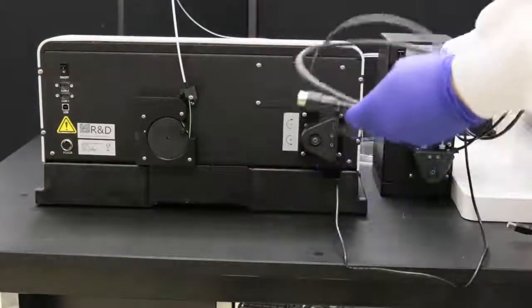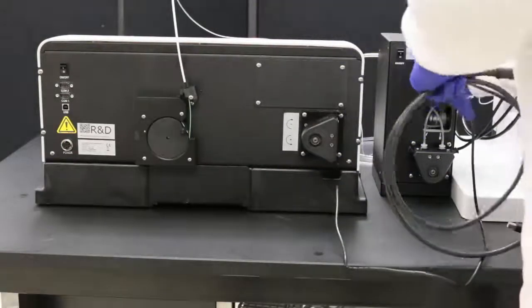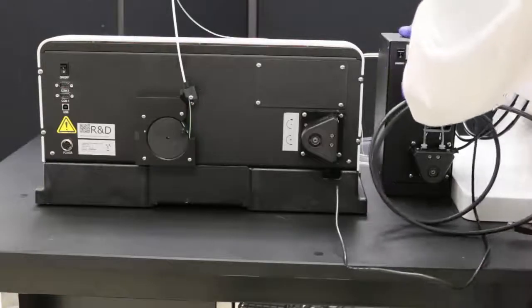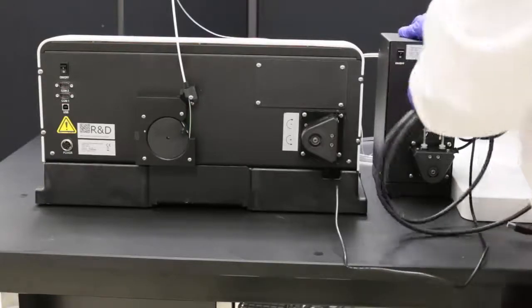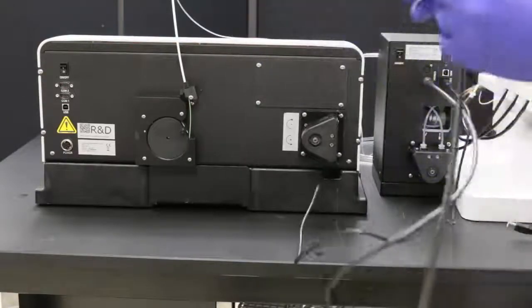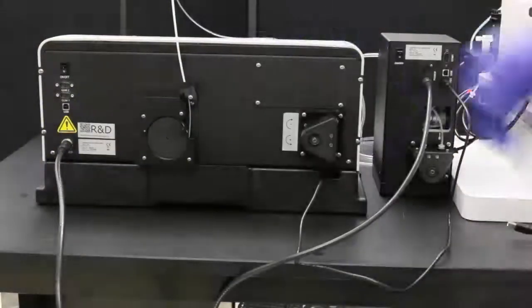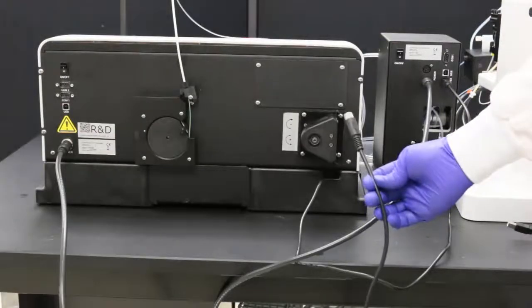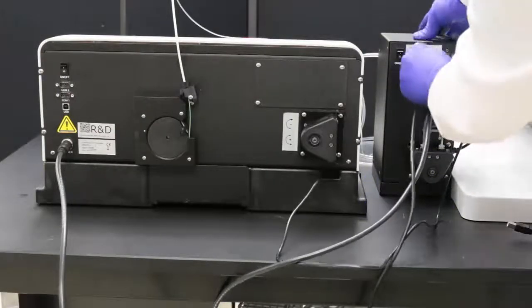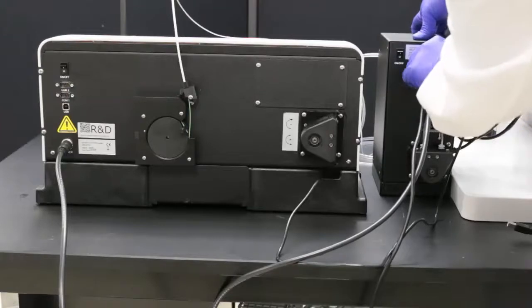Connect the power bridge cable between one of the power ports on the back of the SDX and the auto sampler. Connect the USB cable between the SDX pump module and the computer.